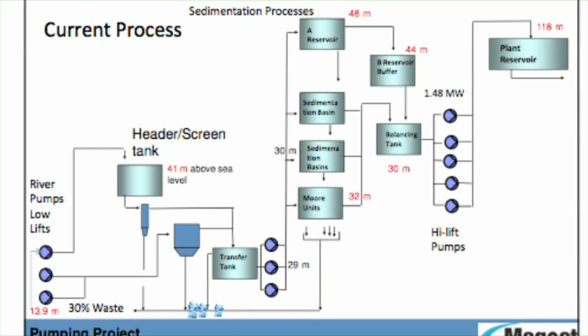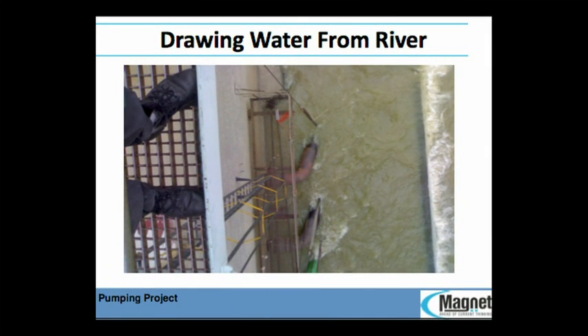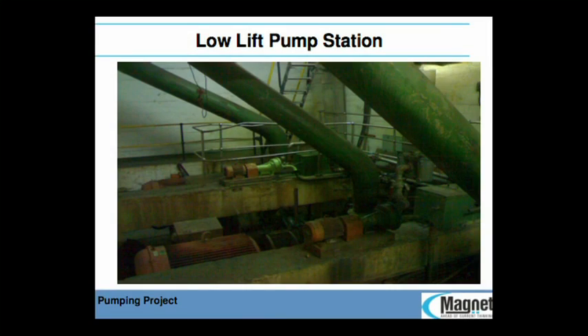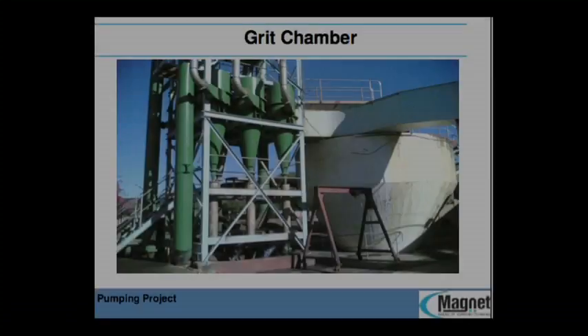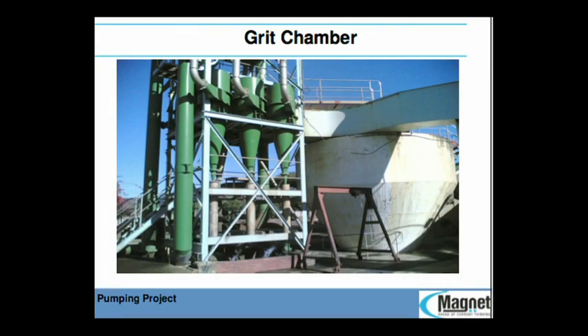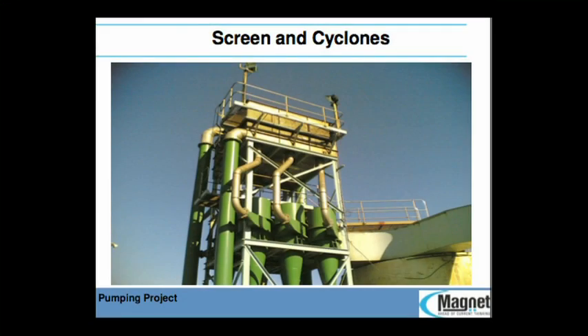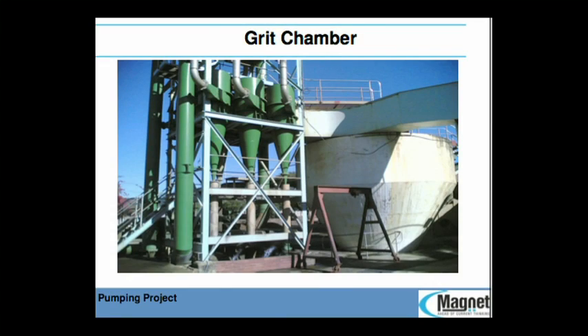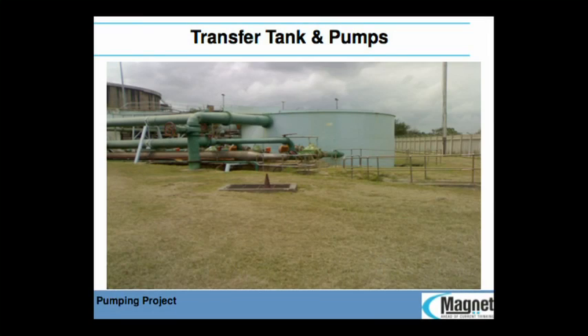Looking at the static heads, you can see we're starting at about 13.9 meters above sea level, 40 meters, and up to 100 meters above the plant, up at the mill. In picture form, this is suction from the river. Those are the 3 pumps drawing from the river up to this chamber on top, which is like a header tank. These are the cyclones. There's their own homegrown centripetal grit chamber. They made this themselves because they didn't feel like buying it from anyone, so they designed it themselves. There's the transfer tank, with 3 original pumps in parallel.